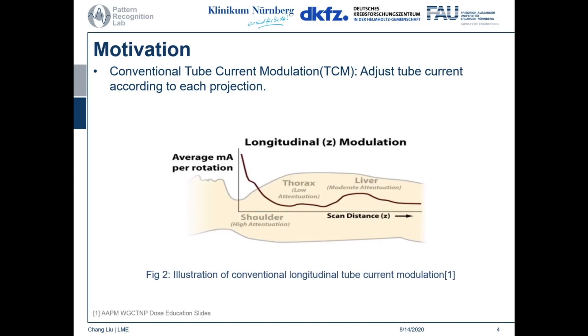Similarly, in the longitudinal direction, we can also modulate the tube current according to the average attenuation of each z position. In this way, we can optimize the dose exposed to the patient during the CT scan. However, conventional tube current modulation treats all human parts equally, meaning the differences between organs and other human tissues are not considered at all.